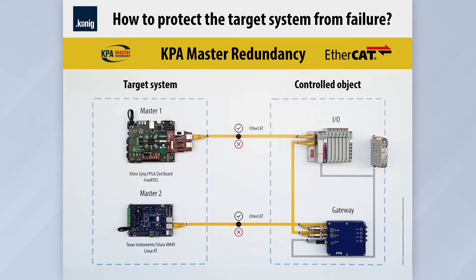The active master sends datagrams to the network and sequentially exchanges information with slave devices, while the passive master operates in sniffer mode, listening to the network and passing information through itself without any changes. At the same time, the passive master synchronizes its own cycle with the active master.